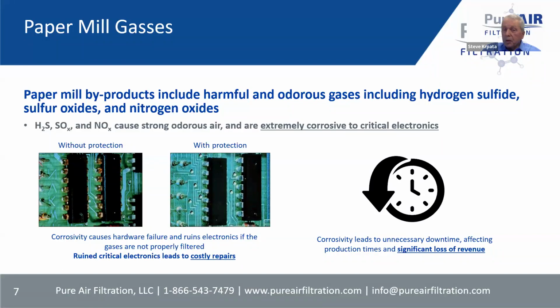A lot of what we'll hear about today is basically trying to get your air into a G1 status, which is an ISA designation. ISA was created by electronic equipment manufacturers to grade air G1, G2, G3, GX, because they were seeing a lot of failures and warranty applications. If you don't have G1 air, they can basically walk away from whatever warranties you think you have on your equipment, and you don't want that. So we want to help you fix it, and we can make sure you consistently receive G1 air in your applications.